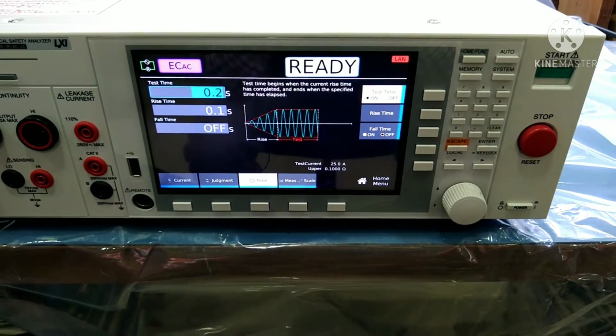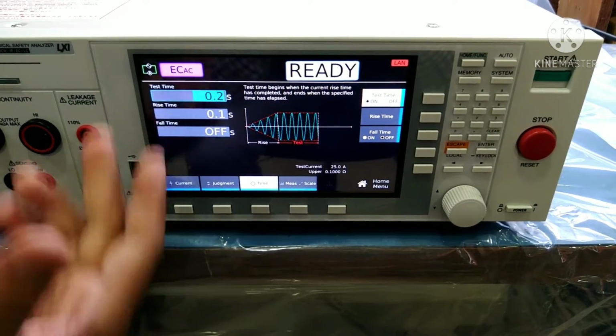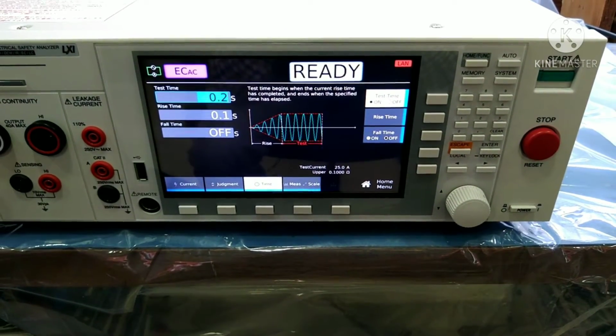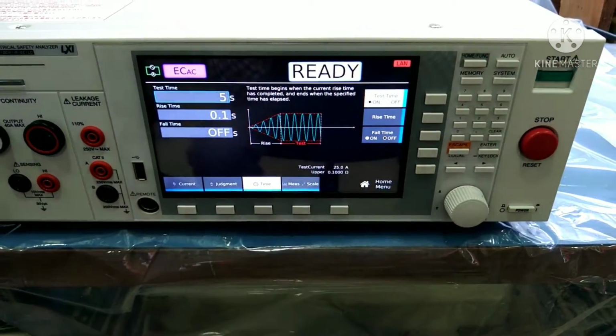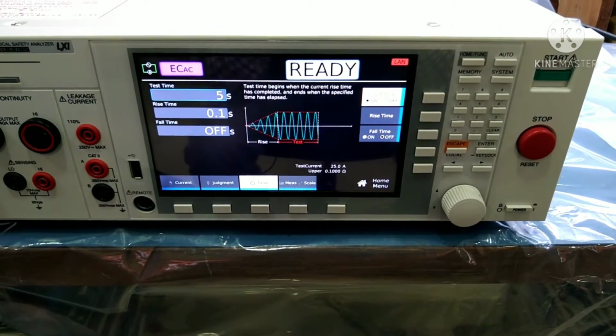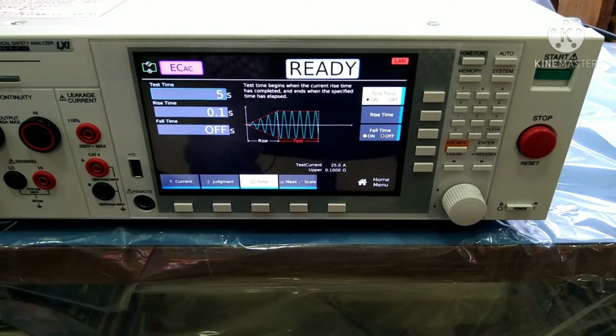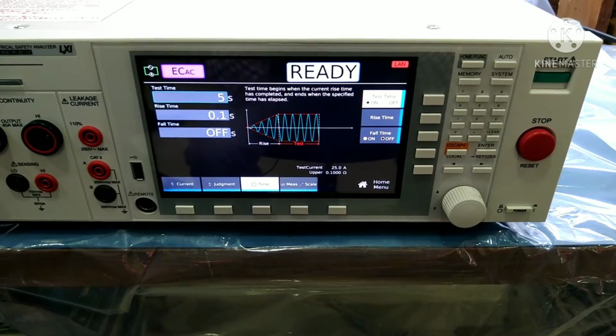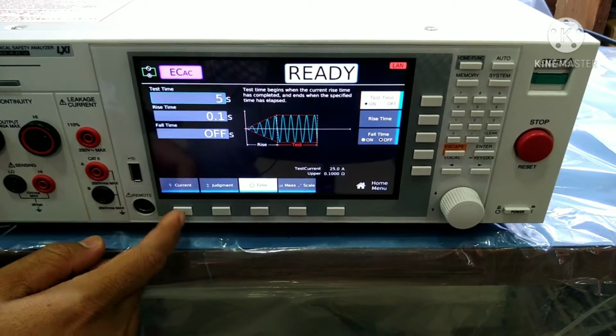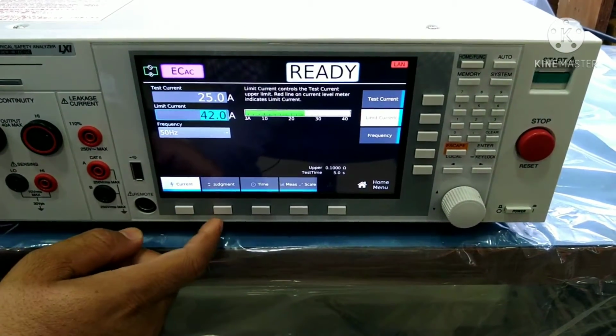Timer: at what time you want to start the test. This is the default setting, 0.2. So I'm going to start for 5 seconds. It will start in 5 seconds and give the result after the 5 seconds. So I'm going to start now. Now it is a ready condition.